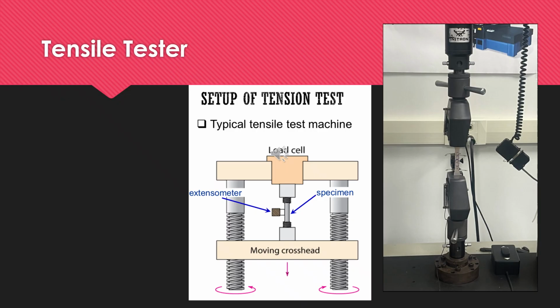The extensometer is a device that we use to get more accurate location of fracture and displacement. It is attached to the specimen itself and does not impact the machine in any way. The machine will pull the specimen until it fractures, and we are left with data in regards to the force, stress, displacement, and elongation percentage.